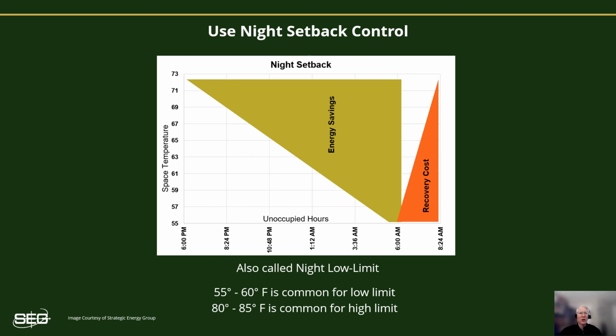Although there may be a few brief periods of operation needed to keep the building from dropping below the night low limit set point. 55 to 60 is a typical night low limit setting. And most systems will also have a night high limit that will function to bring the HVAC on after hours if the building temperature gets too high during the summer. 80 to 85 degrees are typical night high limit settings. Now, most BAS have optimal start, warm-up mode, and night setback capability built into them. We highly encourage all of you to utilize these features. Nevertheless, you will still want to confirm that they're actually enabled for operation and set up to operate properly.